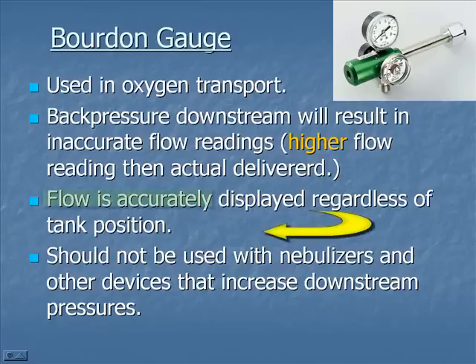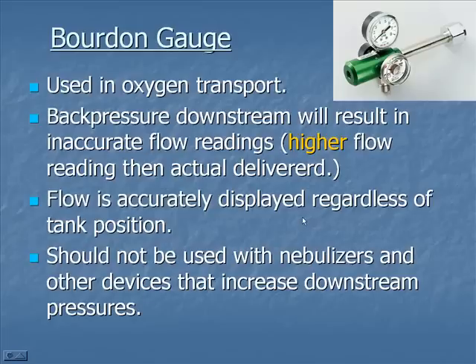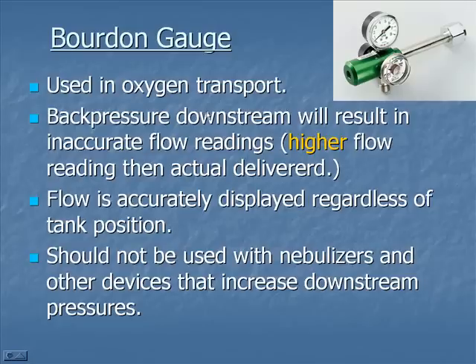However, an advantage of the Bourdon gauge is that it will read accurately regardless of the position of the tank. A Thorpe tube with a little ball cannot be flipped or laid on its side and still read accurately. With the Bourdon gauge, you can lay the tank on its side and still get an accurate reading. These are not really designed to be used with nebulizers because of the back pressure downstream, which could give an inaccurate reading.